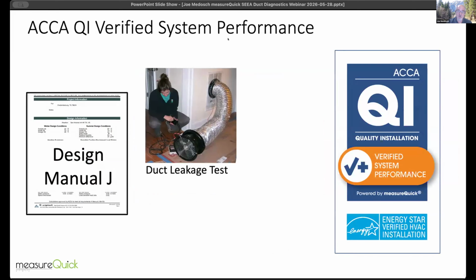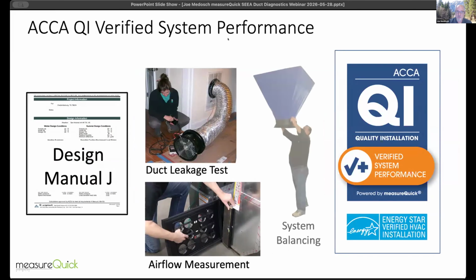And this is nothing new. This has been around since ACCA has been promoting the QI5, which is, again, you're designing your system, you are testing the ductwork, you are doing airflow measurements, and you're balancing. So this is something that's built into MeasureQuick as an option, as the highest performance you can actually do.